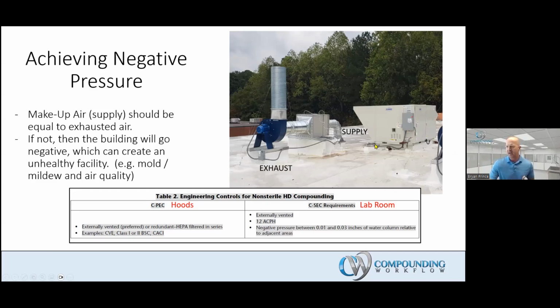It is expensive. These are what I call the unintended consequences of USP 800. I don't know if the expert committee really thought through what this is going to mean, but what this also translates to is another $500 a month on your electricity bill. So not only did you drop $30,000 to $50,000 on the makeup air unit, but now every month you're spending another $500 in electricity because you're pumping, again, perfectly good air out of the building.